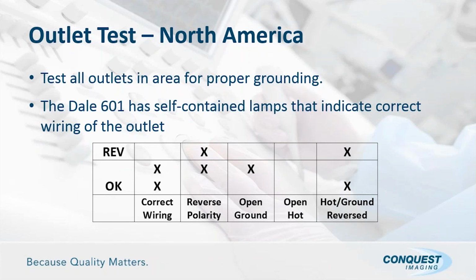And if it's the bottom 2 lights that are on green when you plug it into the wall outlet, it indicates the correct wiring. And I pointed out that the reverse polarity shows the 2 top lights as opposed to the 2 bottom lights. If you have an open ground, it has a single green light in the middle. And if you have the hot and the ground reversed, it gives you the 2 top and bottom lights lit, but the middle one's off. And again, this is on the Dale 601.